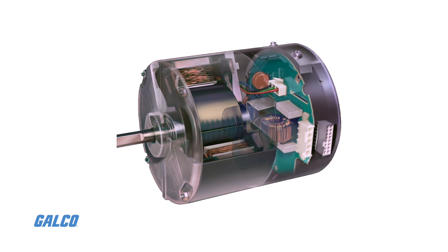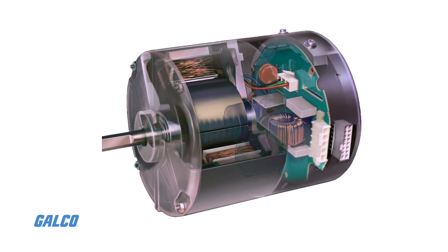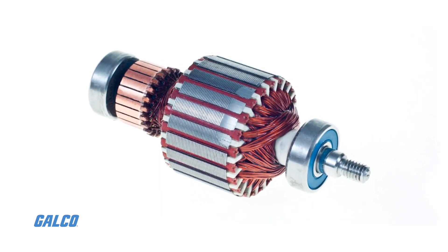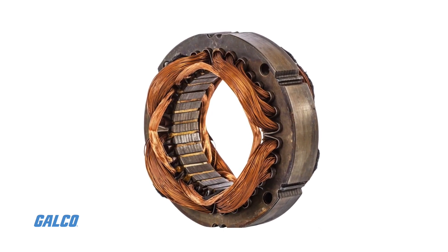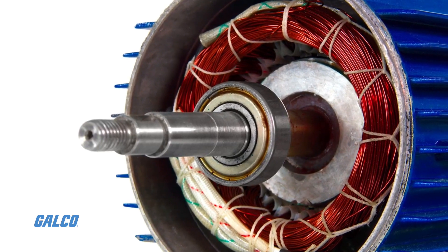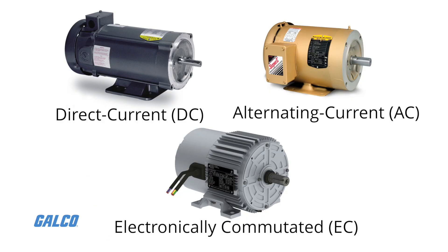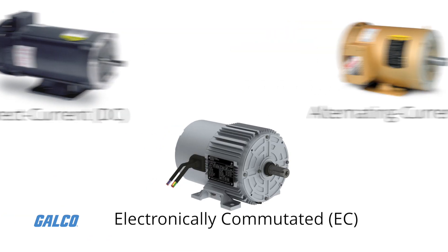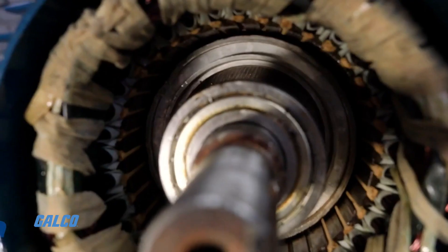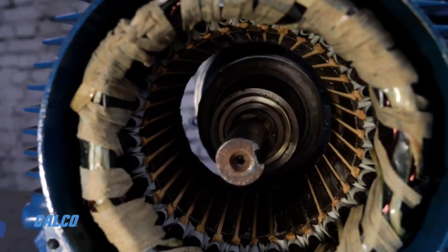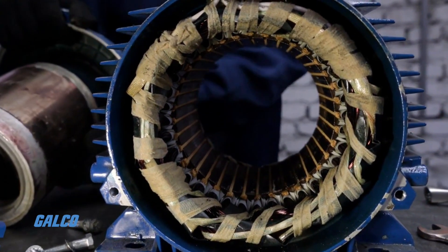EC motors are brushless DC motors controlled by external electronics. The rotor contains permanent magnets and the stator has fixed windings. Electronic circuitry switches the phases in the windings to make the motor turn. EC motors are the most efficient of the three and deliver exceptional control, but they are expensive and current technology limits them to lower power output applications.